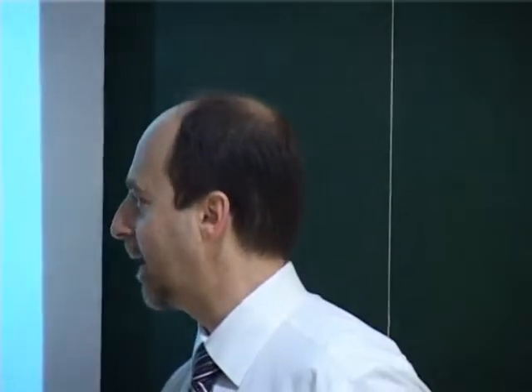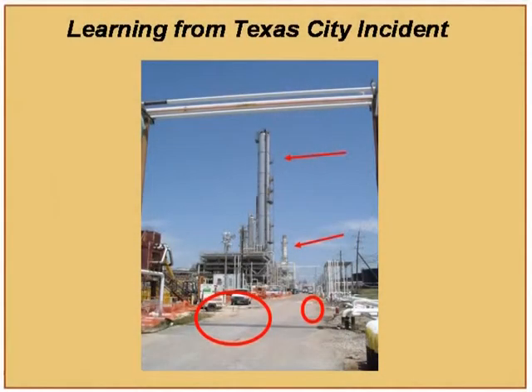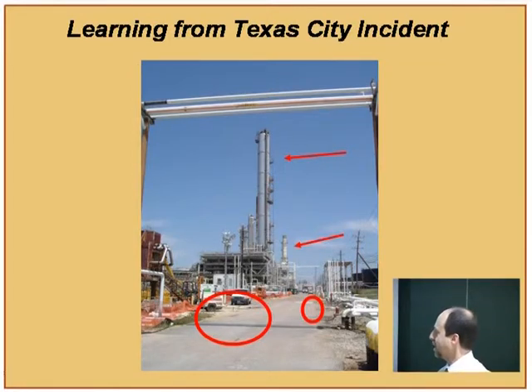Normally, what you really want to do is open the manual bottom valve and put the level of the bottom of the column on automatic control. He did not do that, and began to feed liquid to the column. The liquid accumulated in the bottom and rose higher and higher in the column.